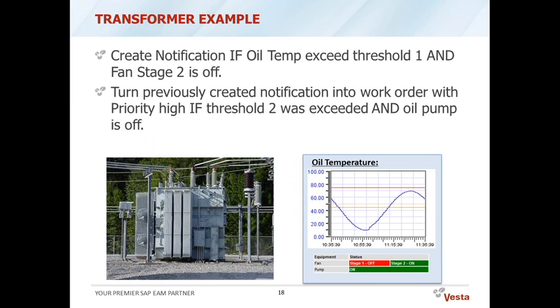What usually happens in a perfectly working system is that a cooling fan kicks in and cools down the temperature, and you would see the temperature turning downwards as we see here in this picture. If the cooling fan is not kicking in, that's usually an indication that either the fan is broken or the sensor to turn on the fan is broken. Either way, you usually want to do something about it, and you want to be notified about that situation.